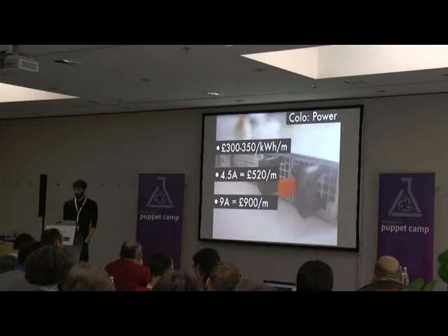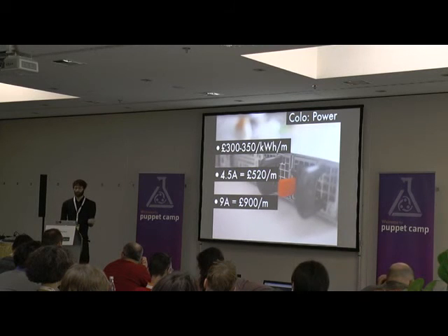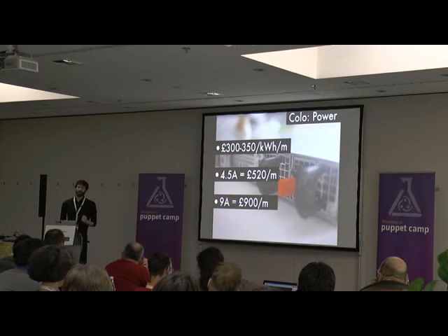And the only way to actually figure it out is to buy your server, buy your hardware, plug it into a power meter, and to actually see what it's drawing when you're running your application on it. Because you can max out the CPUs, as we did in our stress testing, and we were using 1.2 amps. But in normal usage, we're using about 0.6. And you want to make sure you've got the right capacity reserved at the data center to handle that.